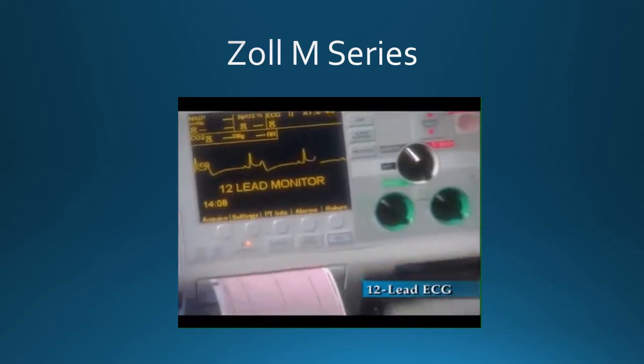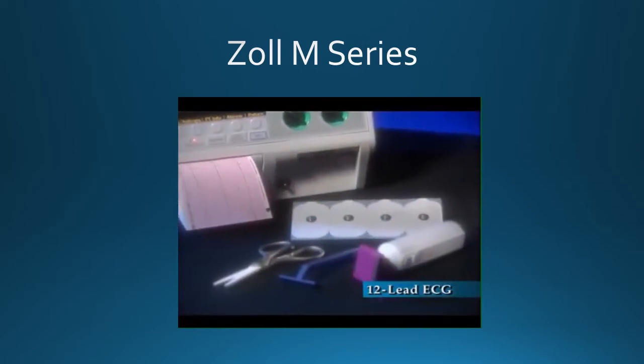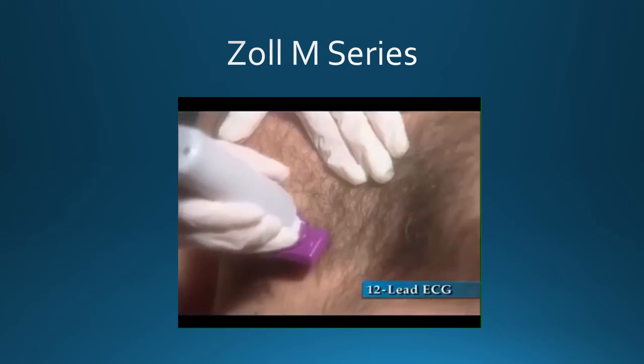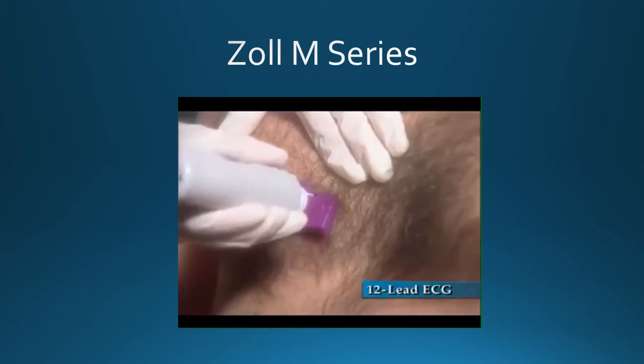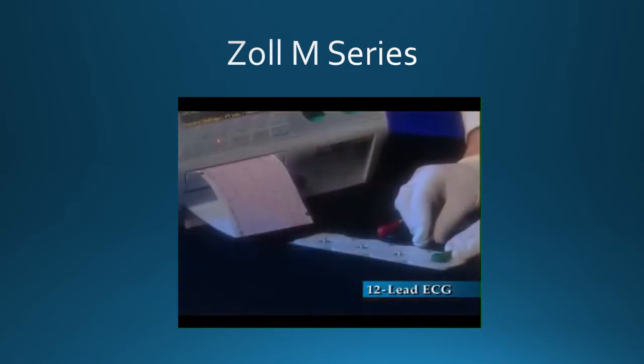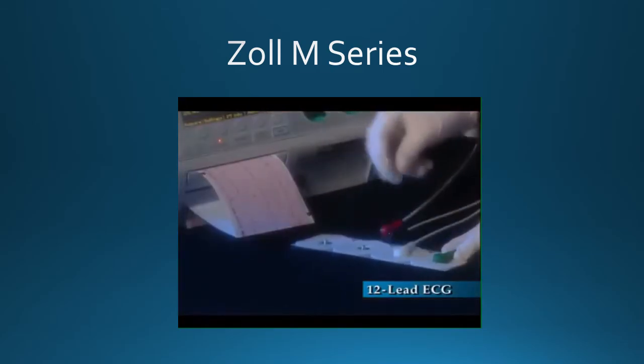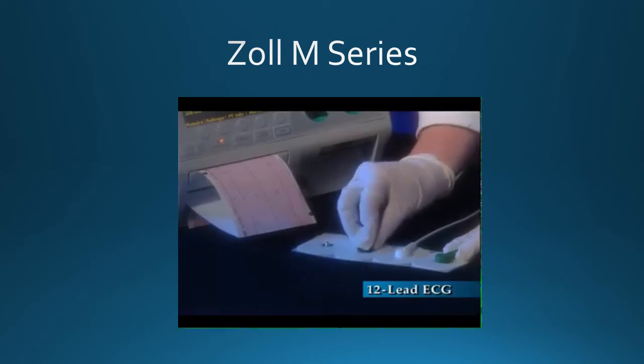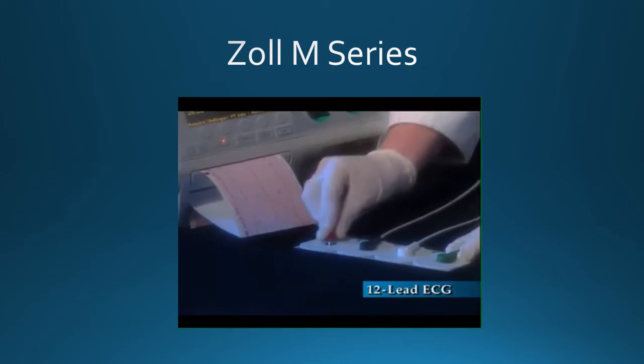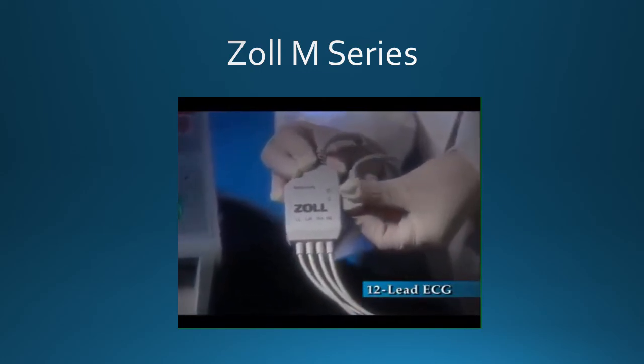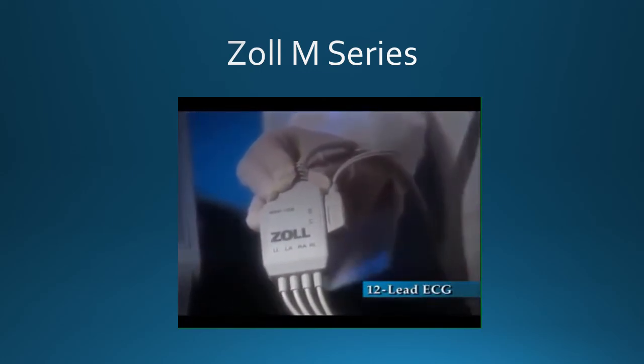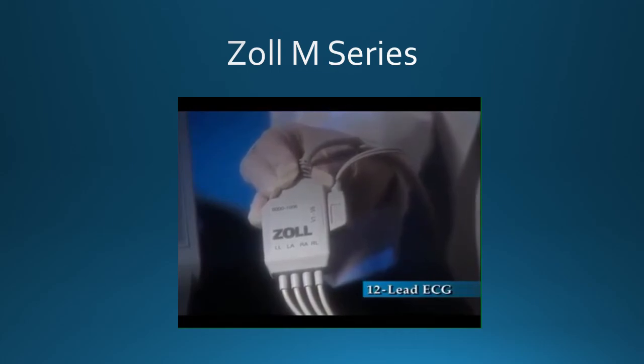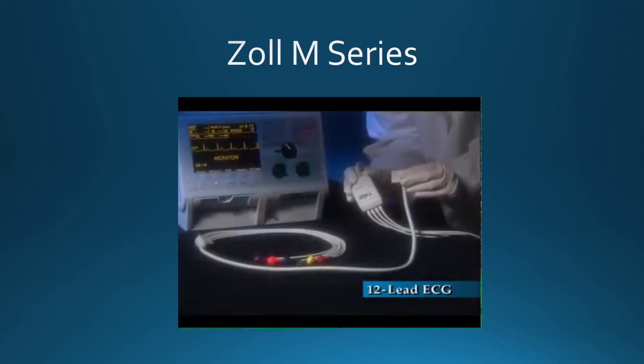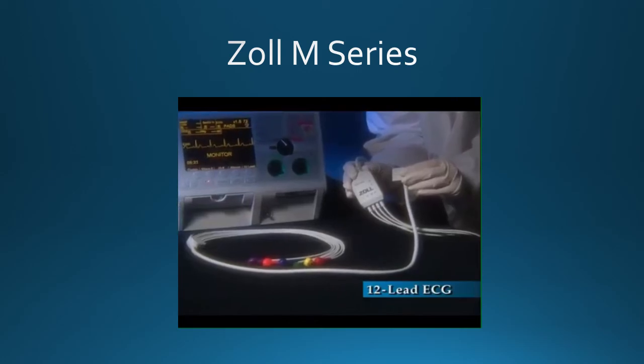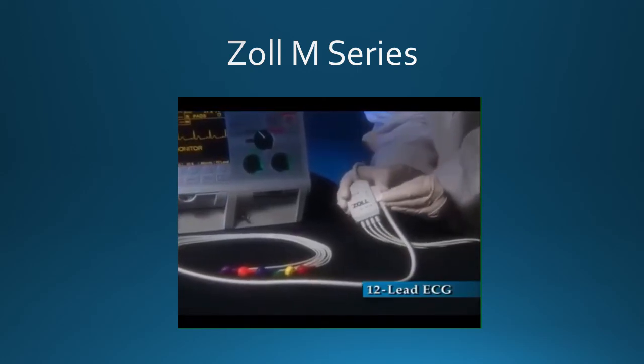Care should be taken to properly prep the patient's skin. This may include clipping excessive hair and light abrasion of the skin to ensure proper electrode contact. High-quality silver-silver chloride electrodes should be attached to the ECG cable snaps and placed on well-prepped skin. When V-leads are not in use, users must plug the protective cap into the V-lead connector on the one-step patient cable. When V-leads are required, the V-lead connector should be pressed securely into the one-step patient cable.